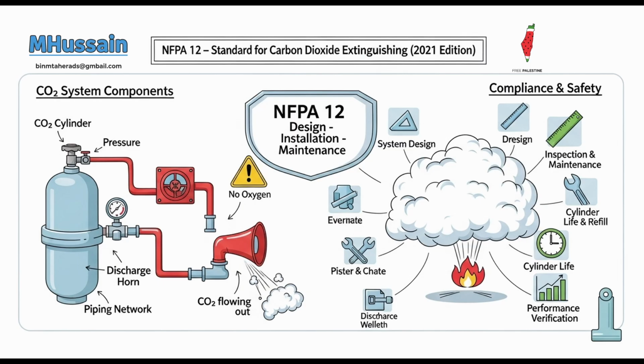Makes sense. What about ventilation you can't shut off? If ventilating systems cannot be shut down during discharge, a challenging scenario, additional CO2 must be added. More gas again. This extra amount is calculated by determining the volume of air moved by the ventilation system during the liquid discharge period, dividing that by the flooding factor, and potentially multiplying by a material conversion factor if the design concentration is above 34%. Complex calculation for leaky rooms. It is. It's a complex calculation to ensure the agent isn't simply blown away before it can do its job.